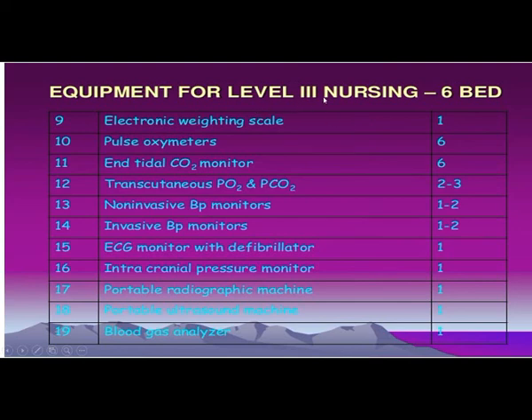And level 3 nursing, that is 6 beds. Other equipment needed: electronic weighing machine 1, pulse oximeter 6, end-tidal CO2 monitor 6, transcutaneous PO2 and PCO2 monitors 2 to 3, non-invasive BP monitors 1 to 2, invasive BP monitors 1 to 2, ECG monitors and defibrillators 1, intracranial pressure monitor 1, portable radiograph machine 1, portable ultrasound machine 1, and blood gas analyzer.